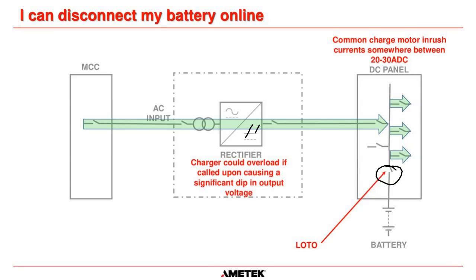So if you absolutely had to quickly replace a battery, you could open the breaker, replace the battery immediately, and your load circuits would still be powered. But if something happened on the DC bus, if things were called into action while you were replacing that battery, all bets are off. We don't know what's going to happen when you have no battery connected.